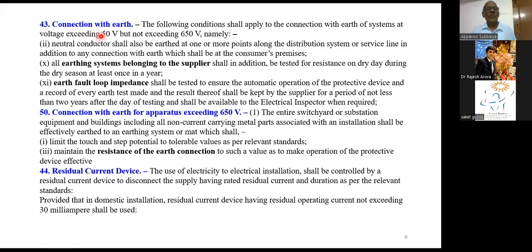Here, what they say, from 50 volt up to 650 volt, this is a provision. One is neutral will be earthed at one or more points along the distribution system or service line, in addition to any connection with the earth which shall be at the consumer, which I have already explained in my previous slide. So this is the supplier's responsibility. They have to earth the neutral conductor at one or more points along the distribution system, or at the service line also.